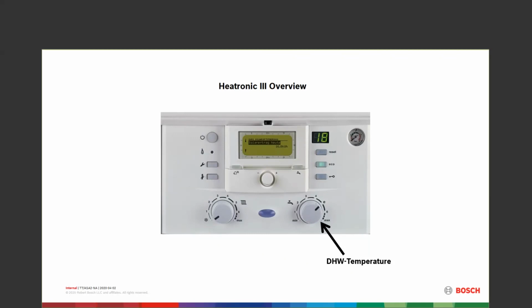So anywhere from 95 degrees all to 158 on a heat only and 140 on a combi boiler. So 6 is 140, max is still 140 on a combi. 6 is about 140 on a heat only with an indirect hooked up to it. Max is 158 on an indirect. That's as much as we can get out of that.